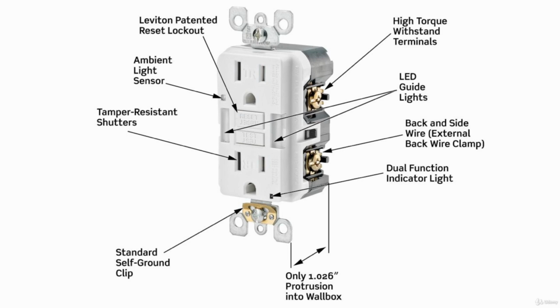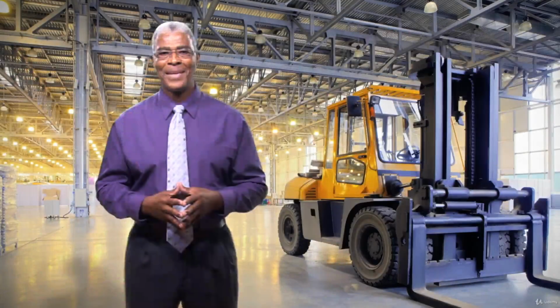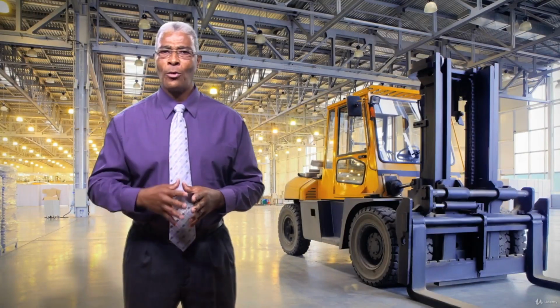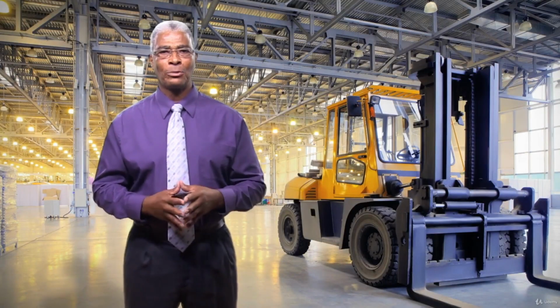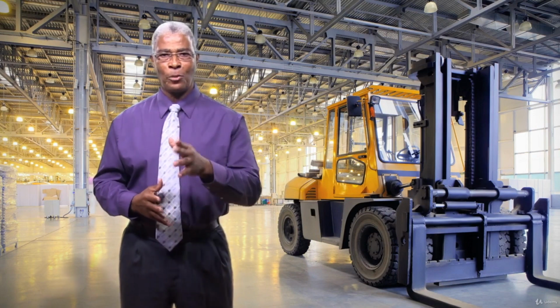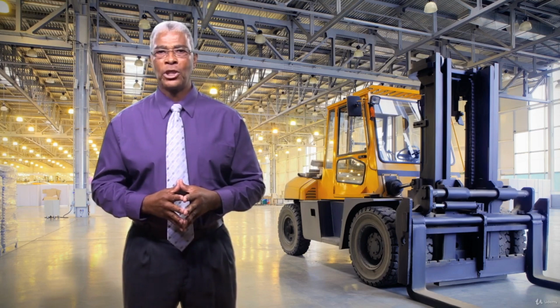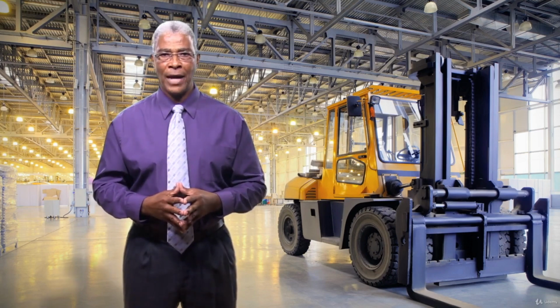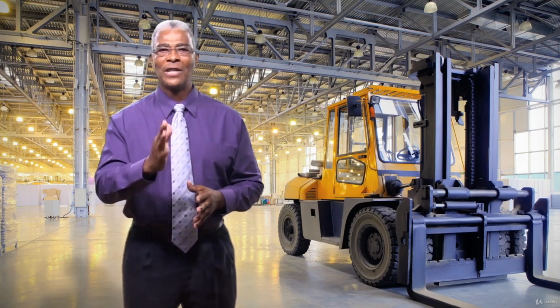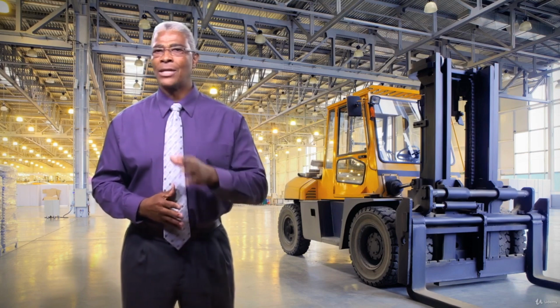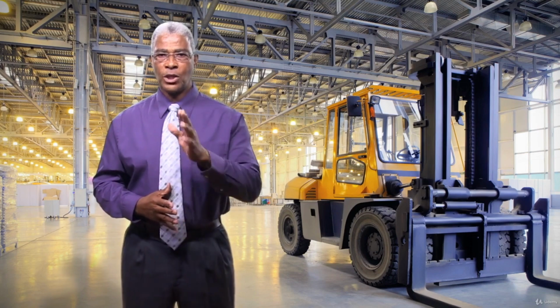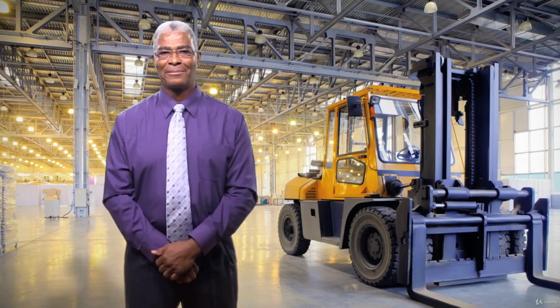Ground fault occurs when there is a break, a leak, or an imbalance in a circuit. The electrical current essentially takes a different, unintended path to the ground, such as through a person's body. GFCIs check that the current going to an electrical device is the same amount of current returning from the device along the electrical path. If there is a 5 milliampere difference or more in the amount of current going to the device and the amount returning from the device, the GFCI shuts off the flow of electricity in as little as 1/40th of a second. This protects the user from dangerous shock.